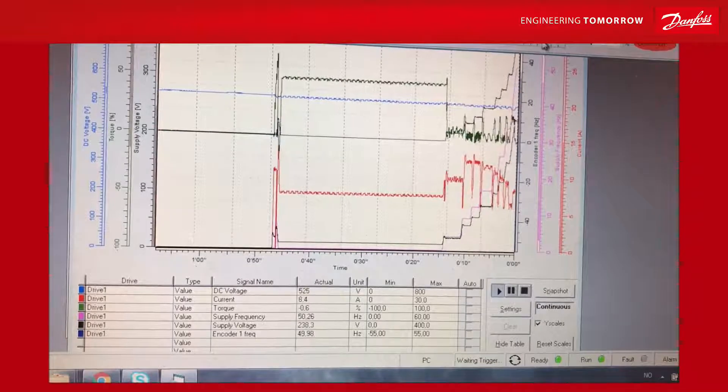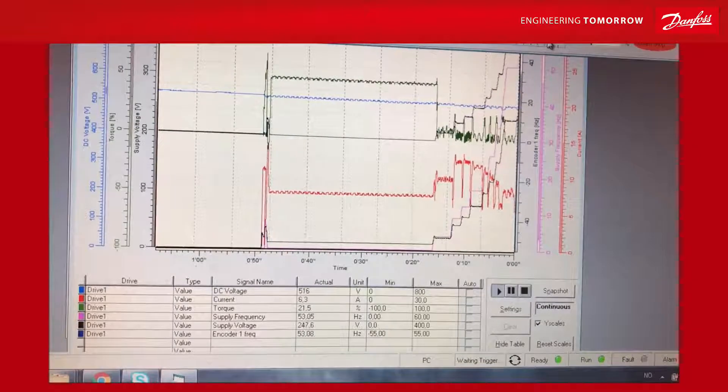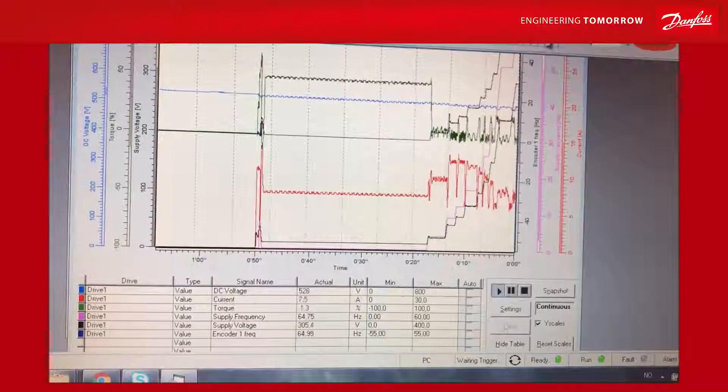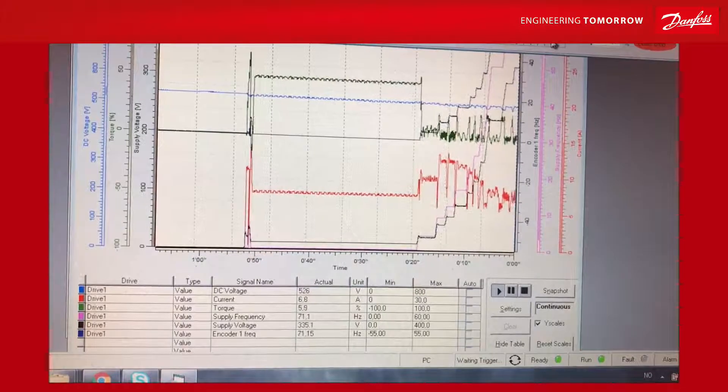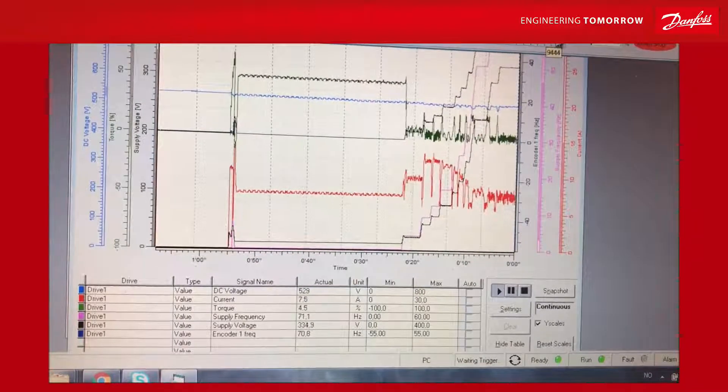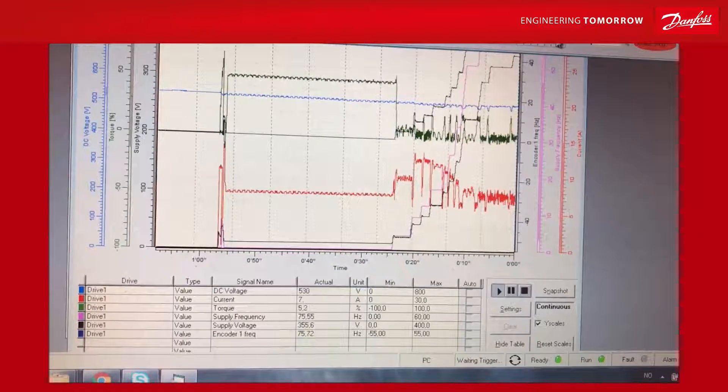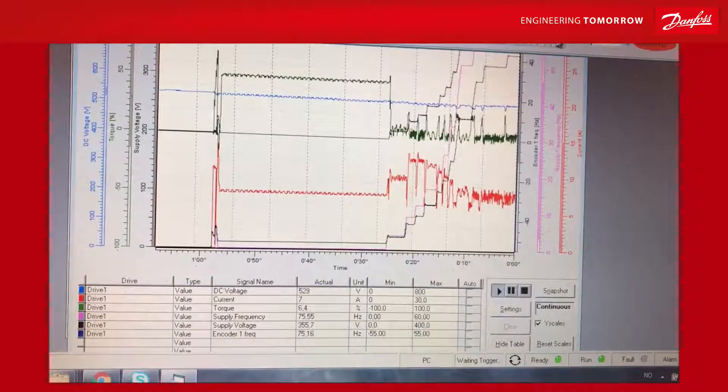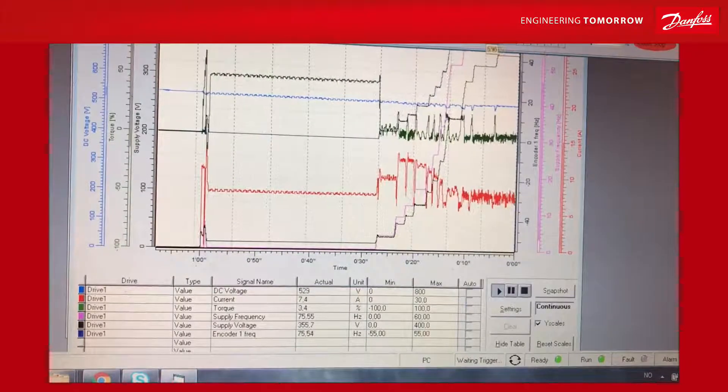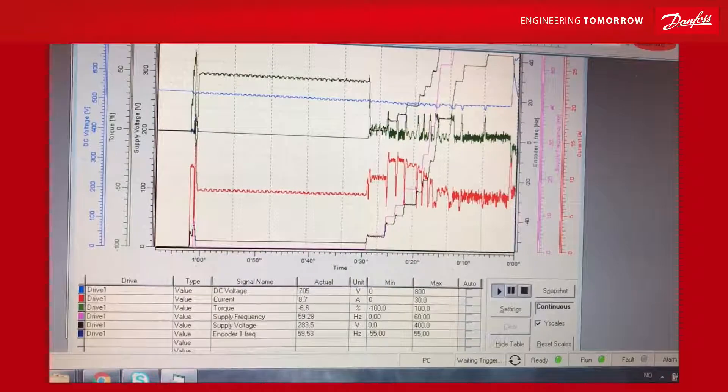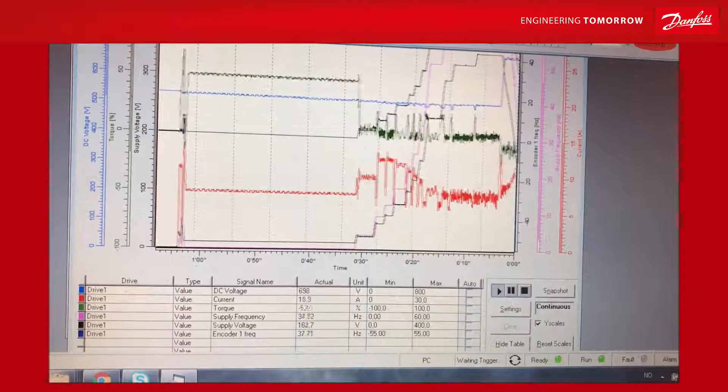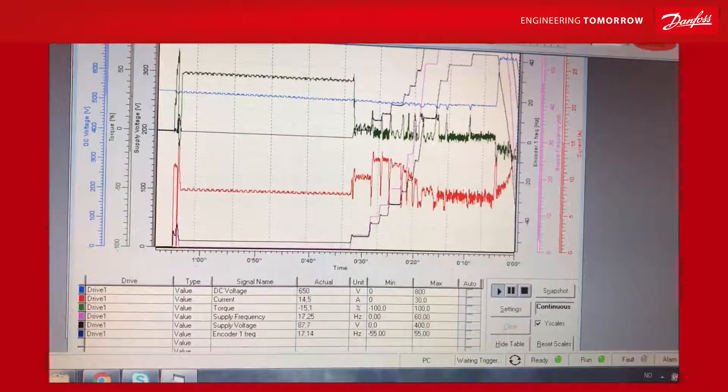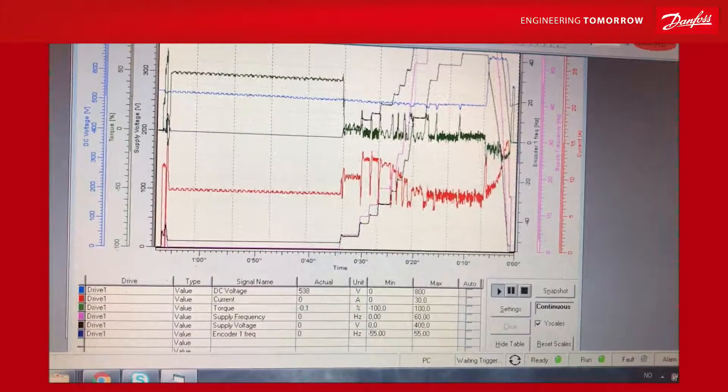I want to run it at quite high RPM to see that there's no vibration or mechanical problems, because the identification run will be at quite high RPM. I want to know that it can do this in a controlled way. Okay, it was successful. So I go back to identification.